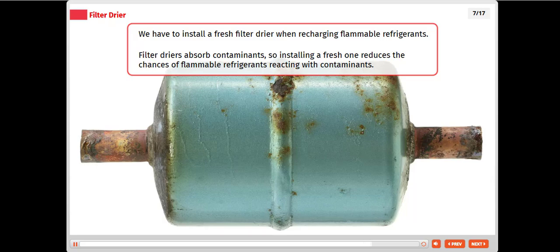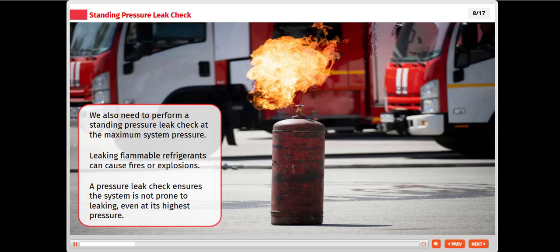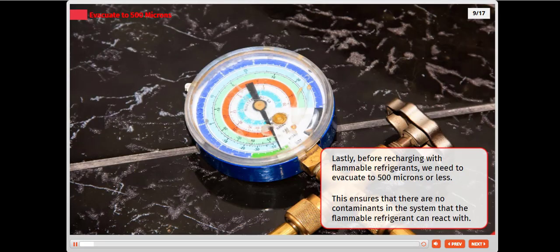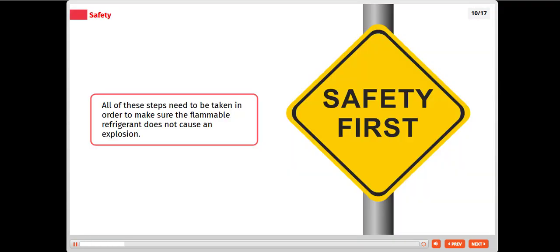We also need to perform a standing pressure leak check at the maximum system pressure. Leaking flammable refrigerants can cause fires or explosions. A pressure leak check ensures the system is not prone to leaking, even at its highest pressure. Lastly, before recharging with flammable refrigerants, we need to evacuate to 500 microns or less. This ensures that there are no contaminants in the system that the flammable refrigerant can react with. All of these steps need to be taken in order to make sure the flammable refrigerant does not cause an explosion.